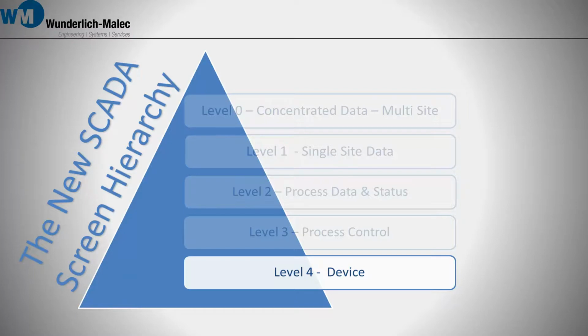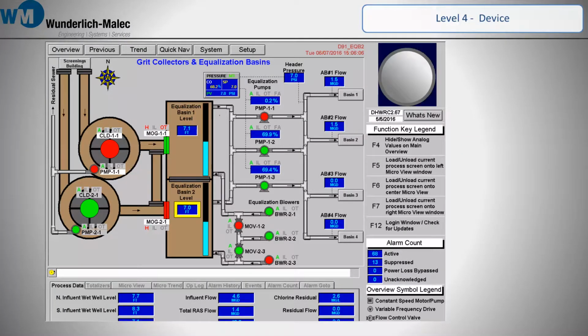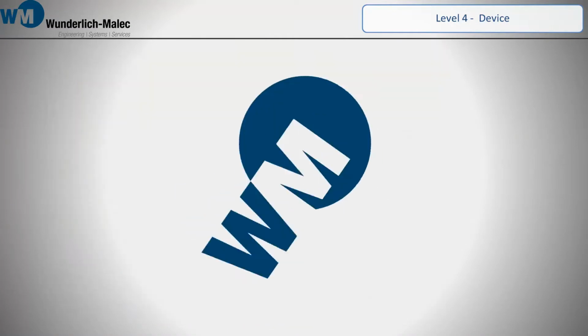Level 4 is now less distracting and more efficient. It shows devices in relation to the layout and their functionality. In the traditional Level 4 screen, we see all the equipment and a significant amount of color to show the status, but is red an alarm? Is it normal operation, or is it off? Current PVs are shown, but if we want a trend, we have to select the ones we want, and then navigate to the trend screen.